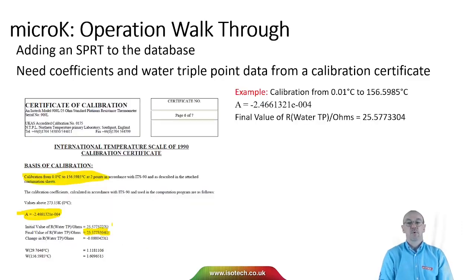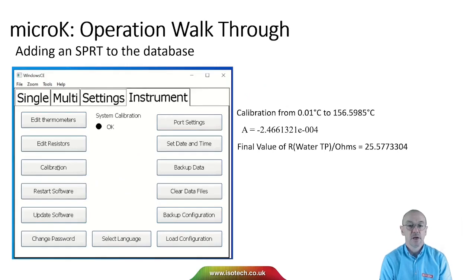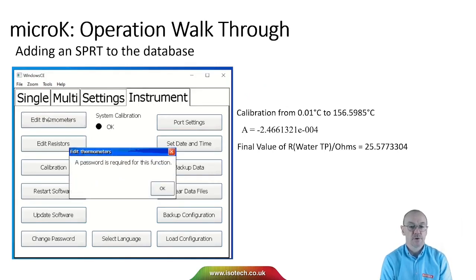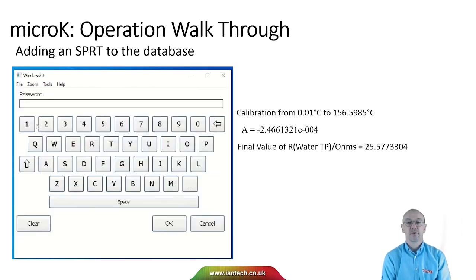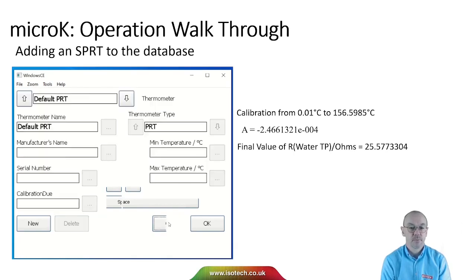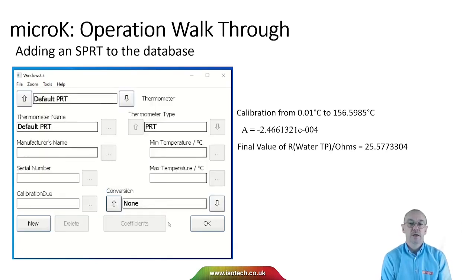But in this example, we're going to go from the water triple point to the freezing point of indium. And we just need a single coefficient, A, and the water triple point resistance of the SPRT. So I can take those from my calibration certificate and pop those into the MicroK. So select Edit Thermometers, password protected, the default password's 1234. We can of course change that to our own value in the settings. And now I can add a new SPRT to the database.